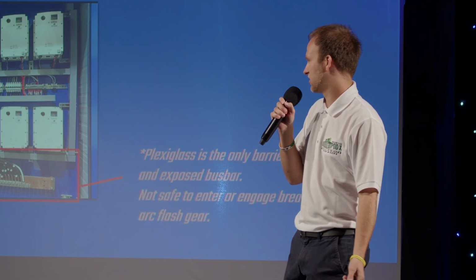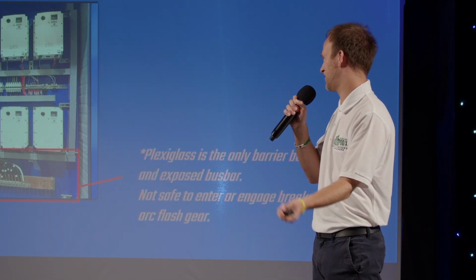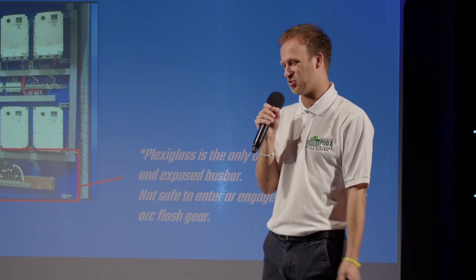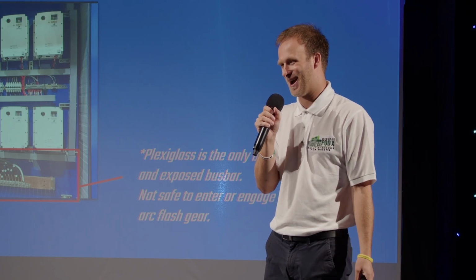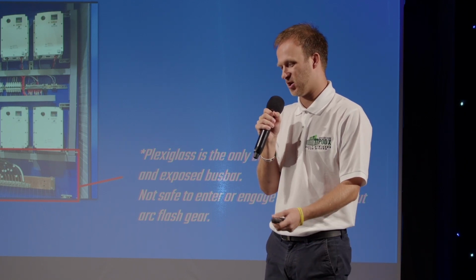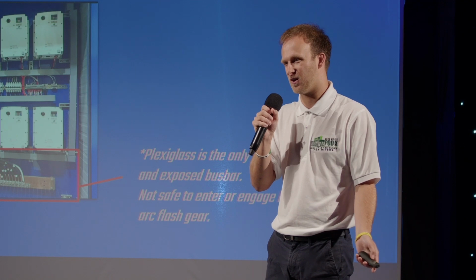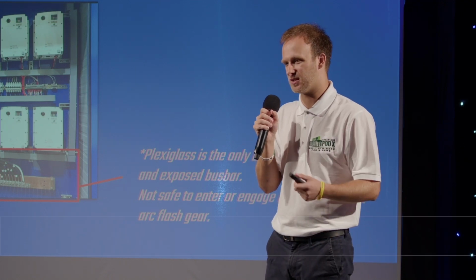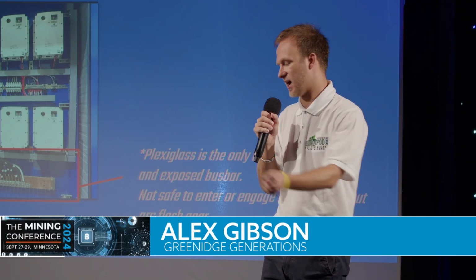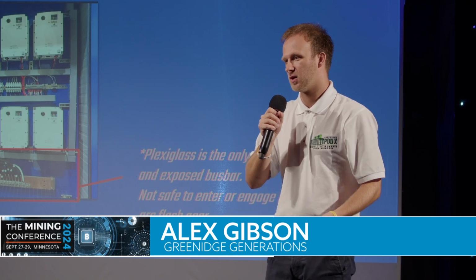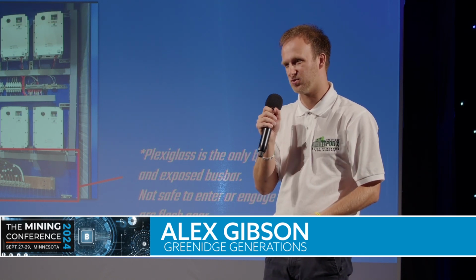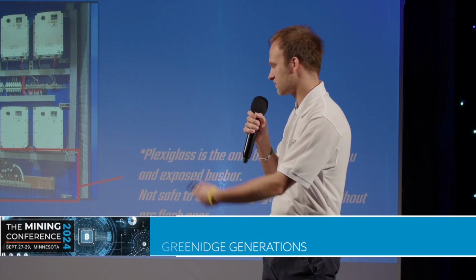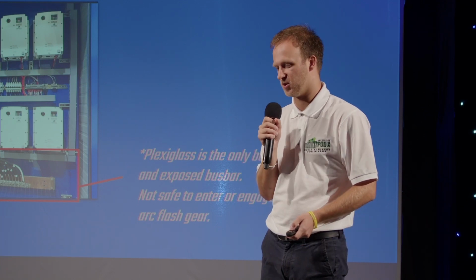And then probably the most egregious error is that you have exposed bus bar, which is a huge no-no. That is very high arc flash potential. If you see any exposed bus bar at all, it's not going to be good. You need to keep that arc flash potential down. It wouldn't be safe to even operate any of the switches in here without using a full arc flash suit. So it's just something to be aware of.